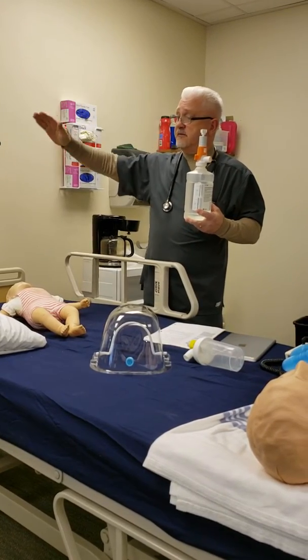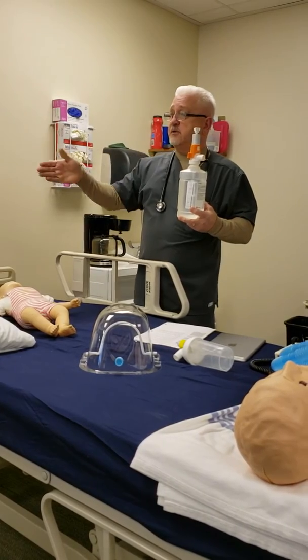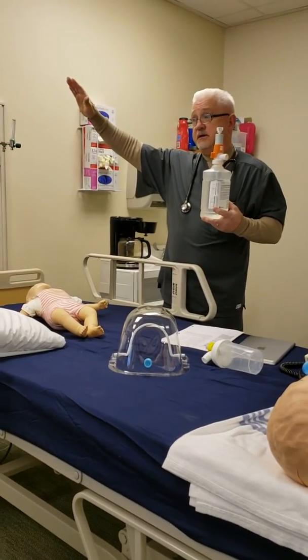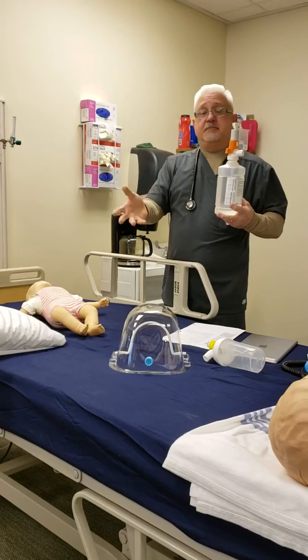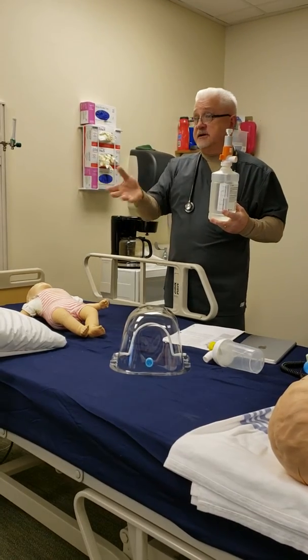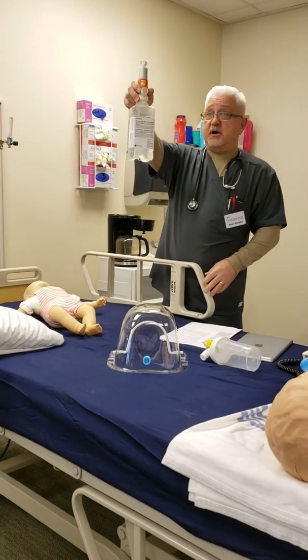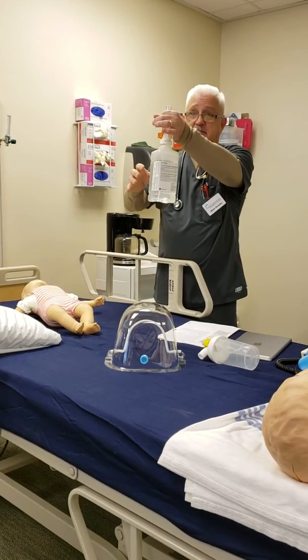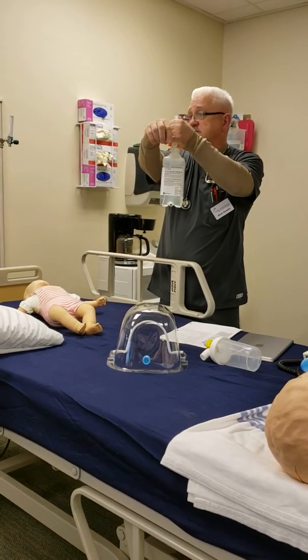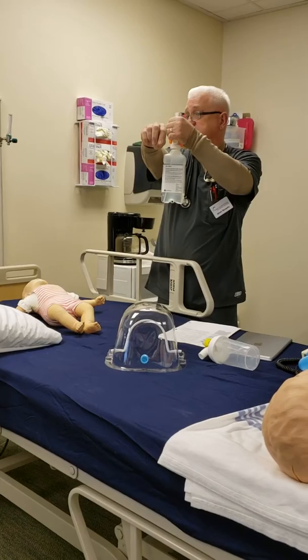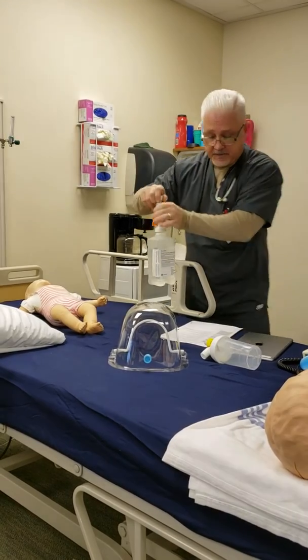Actually, the gas goes over the top of the water that's been heated, and as the gas goes over the top of the water, it picks up heat and moisture to give to the baby. But if we were going to use this, we'd put a heater collar around the top and then measure the temperature of the gas closest to the patient, down proximal to their face.